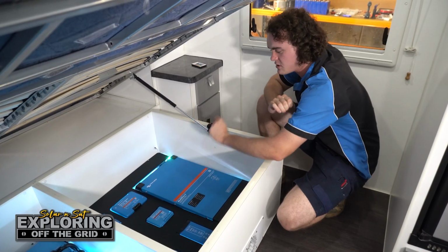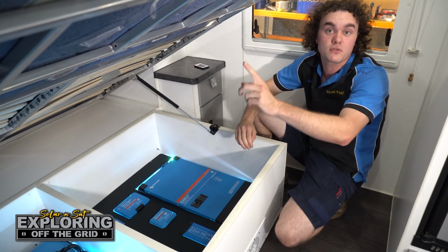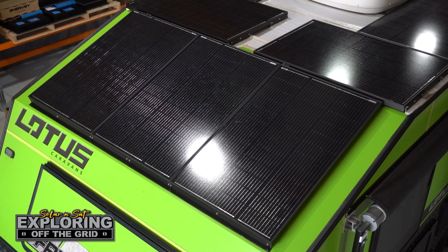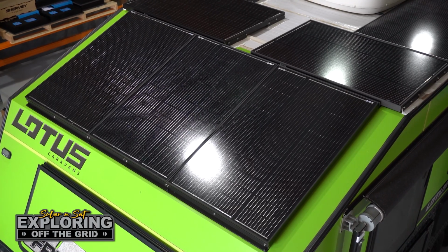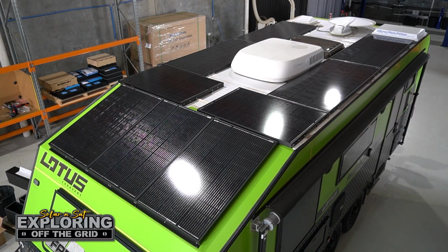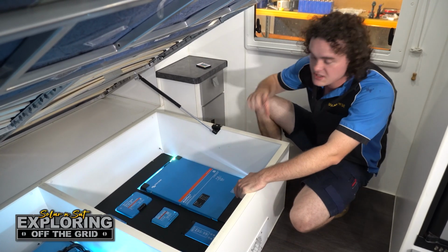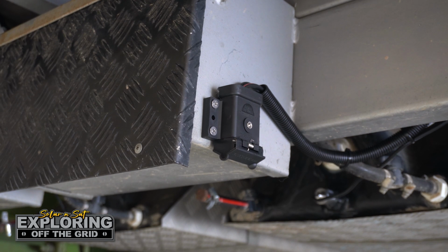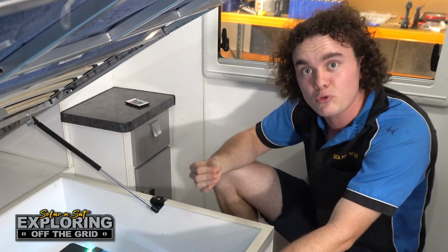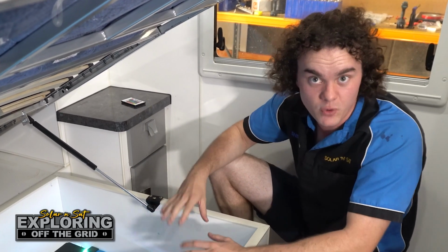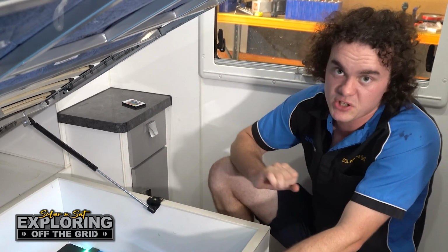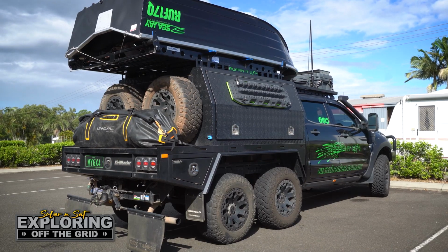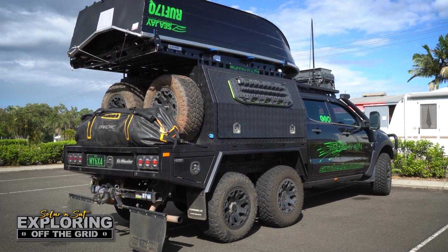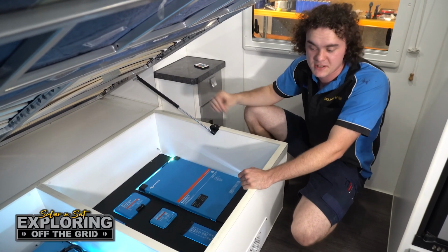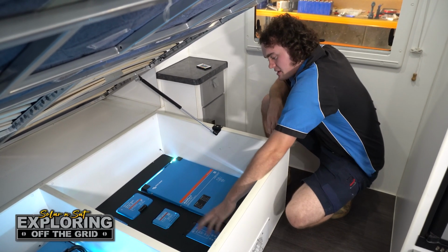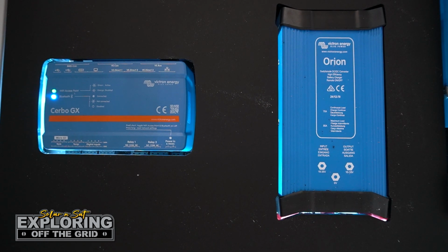Then we've got the 20 amp solar controller, which takes care of the 330 watt panels at the front. Being on a different angle, we wanted to separate that from the rest of the solar array. Then we've got the 15 amp solar controller, wired up to an Anderson plug on the outside for a solar panel input. With their portable panel, we've also wired it in series to get 40 VOC, allowing it to charge a 24 volt battery bank. We then modified the input on their car to ensure that same solar panel could also charge their car's system if they chose. Down here we've got a very efficient Orion DC-DC converter.